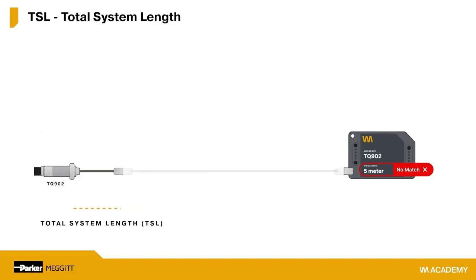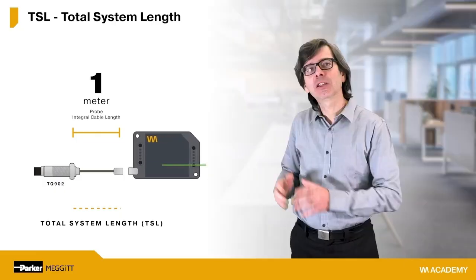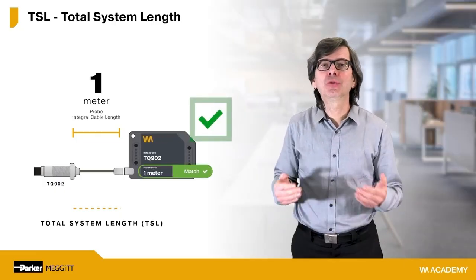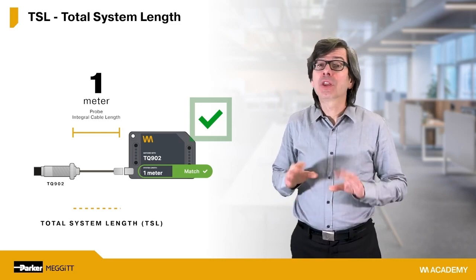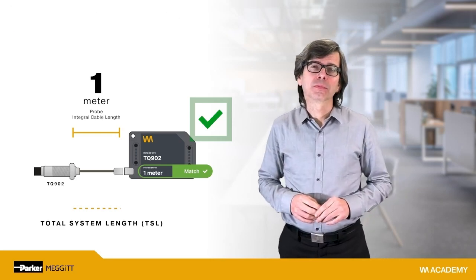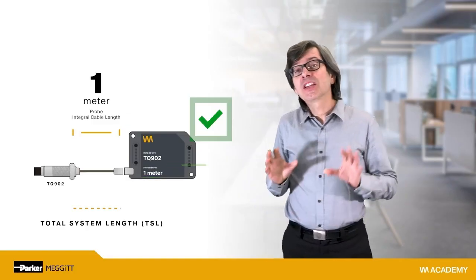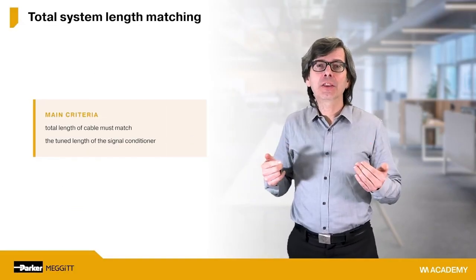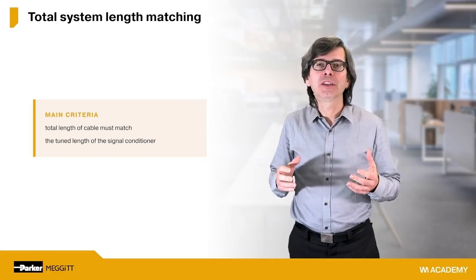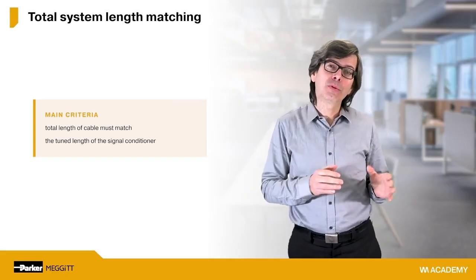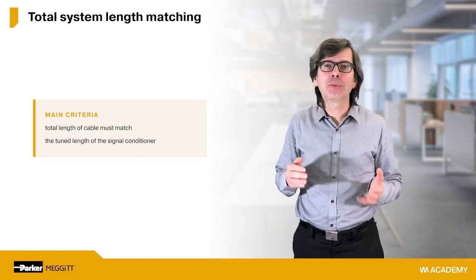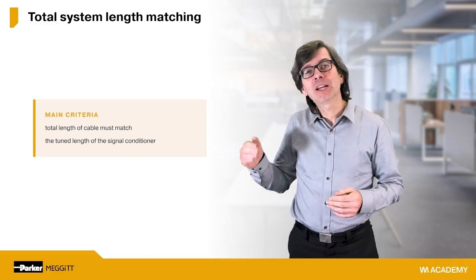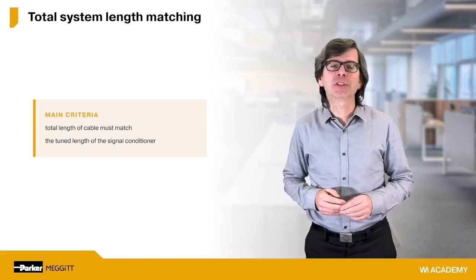In some cases, an extension cable would not be used at all. For example, a probe with a 1 meter integral cable could be connected directly to a signal conditioner which is tuned for 1 meter, without use of an extension cable. The criteria is that the total length of cable, regardless of whether it exists entirely at the probe or as a combination of the probe and the extension cable, must always match the tuned length of the signal conditioner.